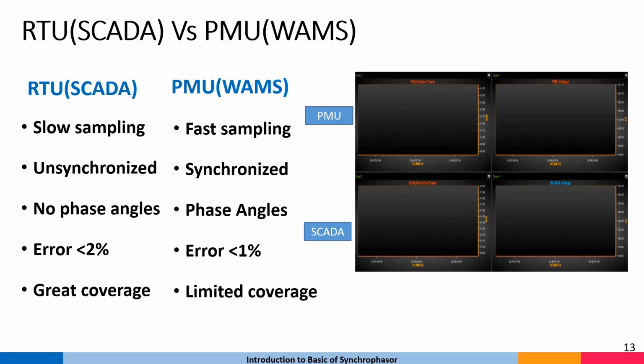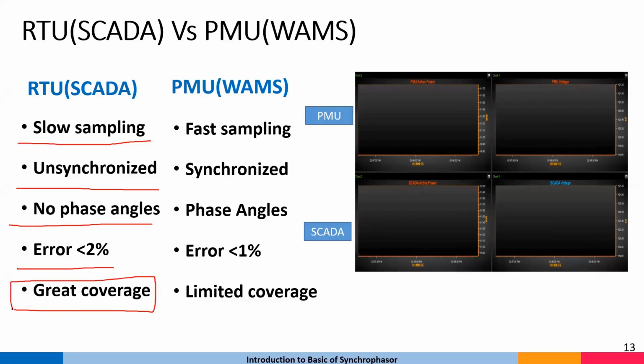However, there is an additional function to estimate the phasor rather than just providing analog to digital sample data. Presently in the control center, earlier we had the RTU based system, remote terminal unit, which is a slow sampling system providing data every 2 to 5 or 10 seconds. It gives only magnitude because it is not time synchronized in real time—the earlier system was based on steady state visualization. It does not provide phase angle, and the data error is less than 2%. However, its coverage was quite great.